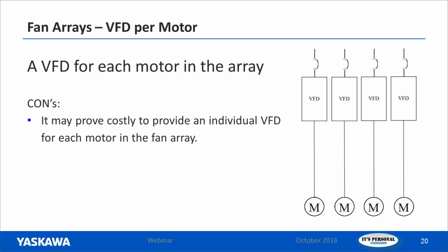Cons, it could prove in some cases costly to provide a VFD on each motor in your array when you're doing an array. It does get done, but it could be costly. This is kind of a lesser con, but I still bring it up. There is a potential for nuisance overvoltage faults. If you end up having a VFD having a call for lower speed than the rest of the motors in the array, the air that's moving through is going to be trying to overdrive that motor that drive is running, and that'll result in an overvoltage fault.